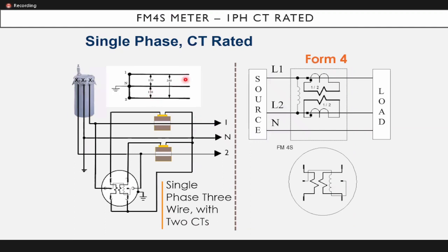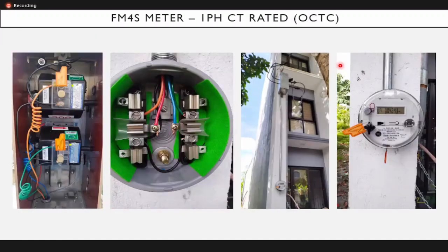Now, for the single-phase CT rated, the meter form to use is Form 4S. This is a typical installation. Ito po siya. Single-phase installation, we have two bushing current transformers or BCTs. Normally, 200:5 ang kanyang CT ratio.